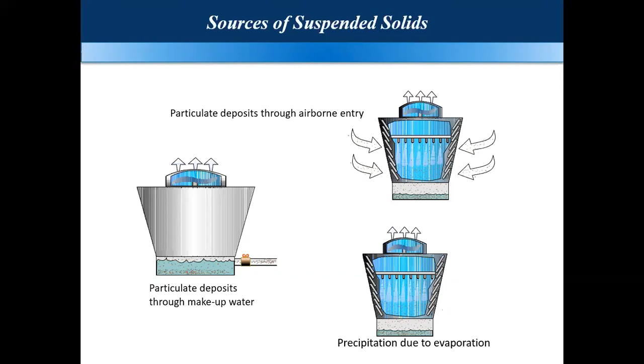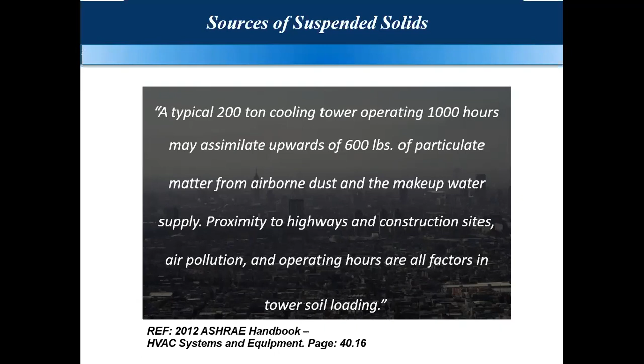Here is a reference from the ASHRAE 2012 handbook, which says a typical 200-ton cooling tower operating 1,000 hours per year, where a year has 8760 hours, can accumulate about 600 pounds of particulate matter from airborne dust and makeup water supply. And what I was saying, the proximity of highways, construction site air pollution, and operating hours are all factors which determine the tower soil loading. If those are high, then your deposition will be from 600 pounds, or 300 kg, to 600 kg.